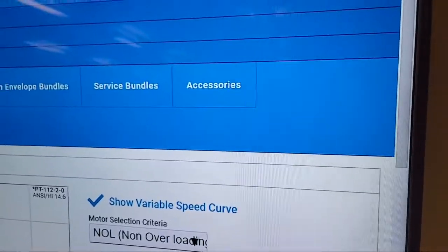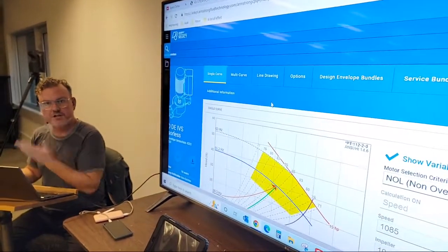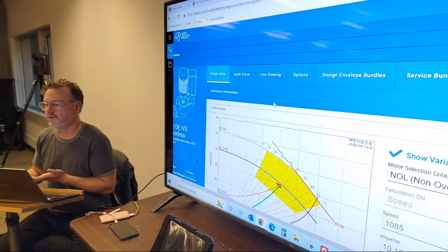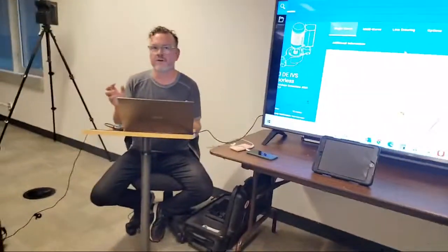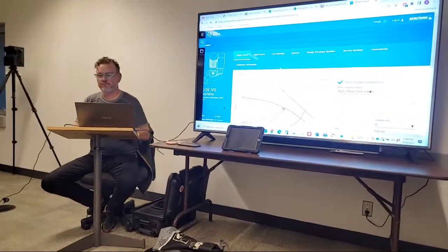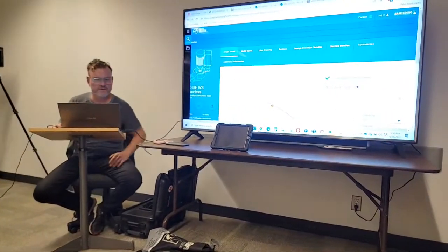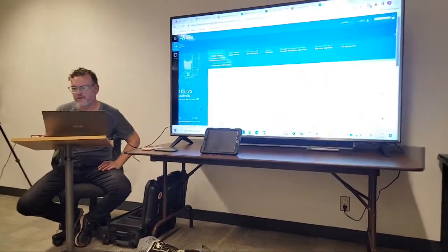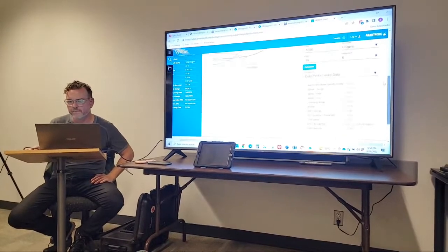Especially that cavitation too, right? You want to not destroy the pump like this. That would be more like somebody coming along and throttling a valve on the suction side. You know, that sudden change in pressure. So basically you get all these bubbles that appear, right? When it goes to vapor, and then when they come back, they explode. So you can actually blow your pump up. The water boils, basically, when the pressure is too low. Yeah, when the pressure is too low.